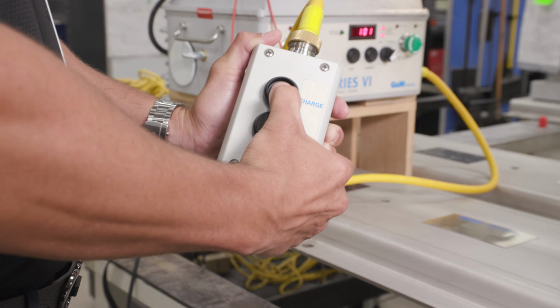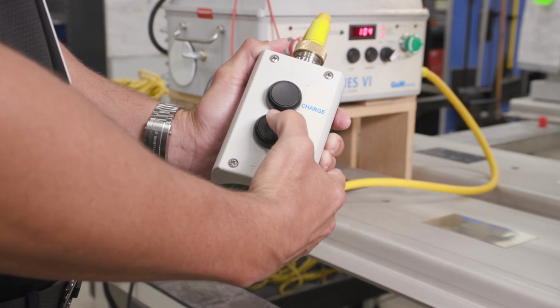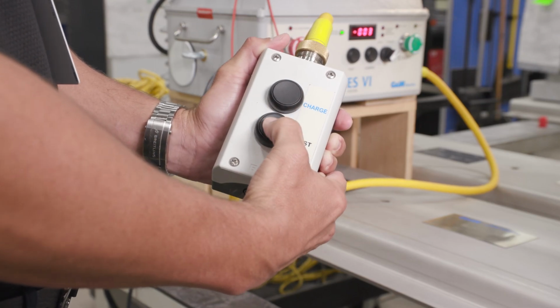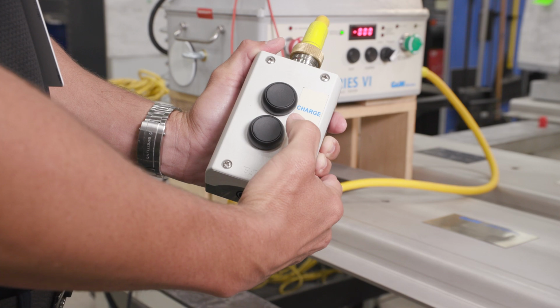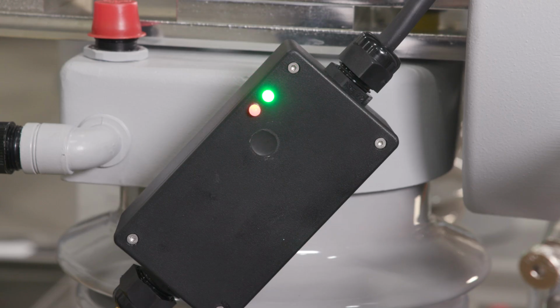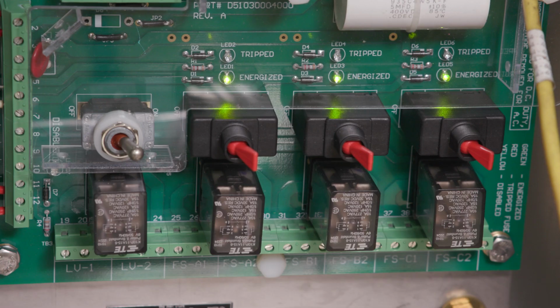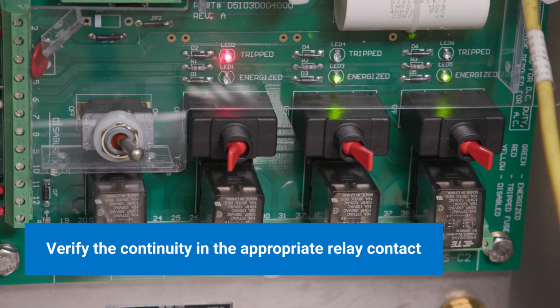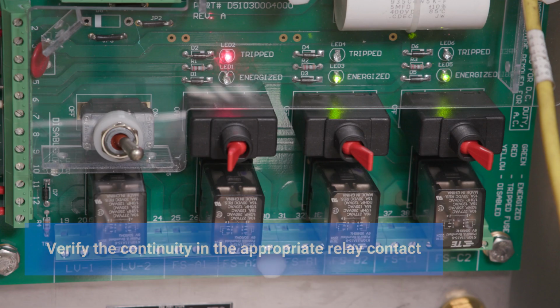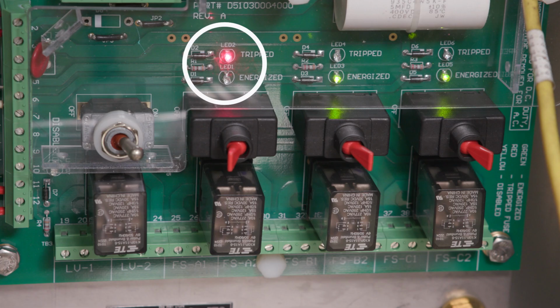Use the field tester to fire the CLiP current limiting protector and confirm that the simulator operates the remote indication feature. A red light will illuminate temporarily in the simulator. The circuit breaker for that phase in the control box will then trip. This in turn will cause the remote indication relay in the control box to activate. Check this by verifying the continuity in the appropriate relay contact. In addition, a red light will illuminate adjacent to the relay and circuit breaker of the triggered phase.